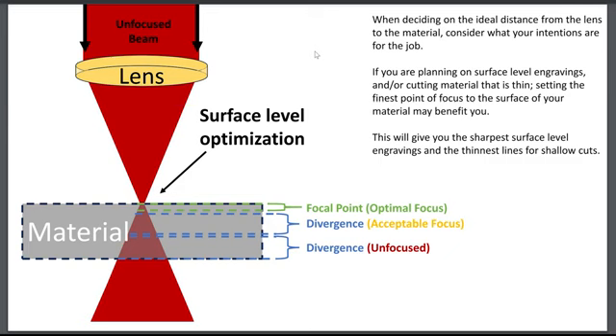But really what happens is the unfocused beam travels down into your laser head and through the lens, which has a special shape, right? As it goes through that lens, that special shape condenses the energy from the beam into a fine point, which is your focal point. And as the energy is condensed, this process is called convergence.